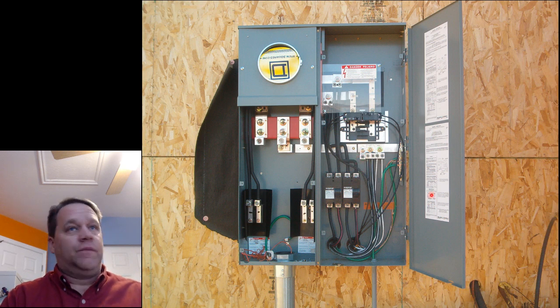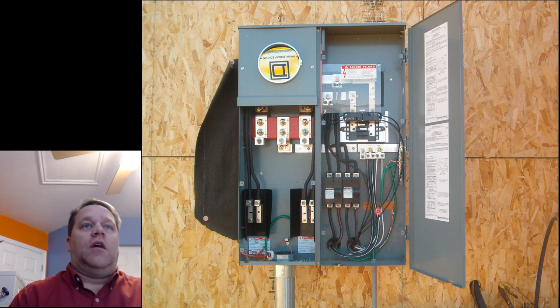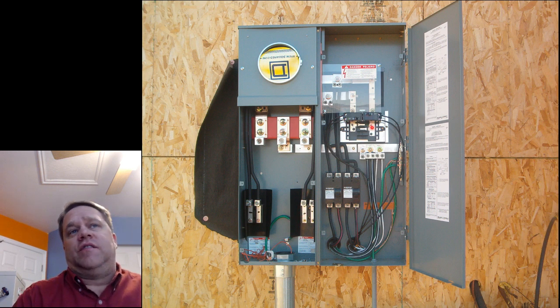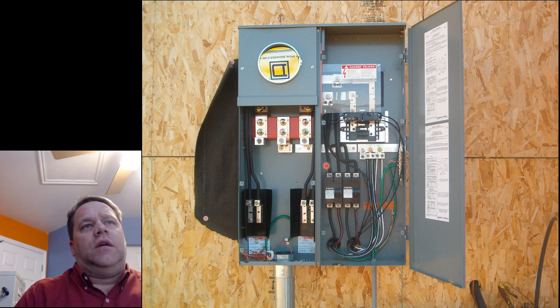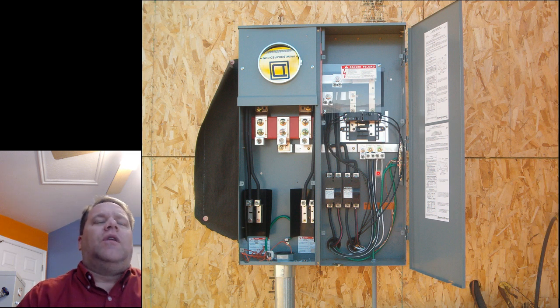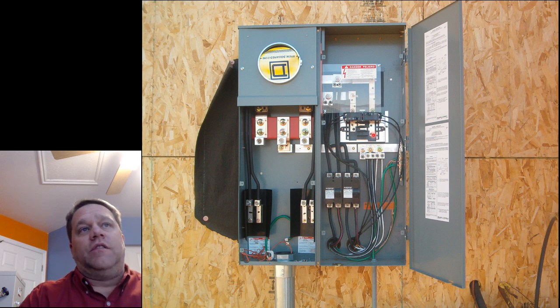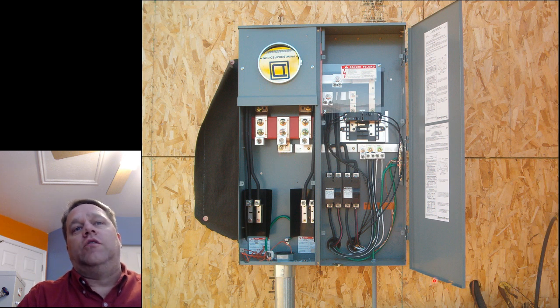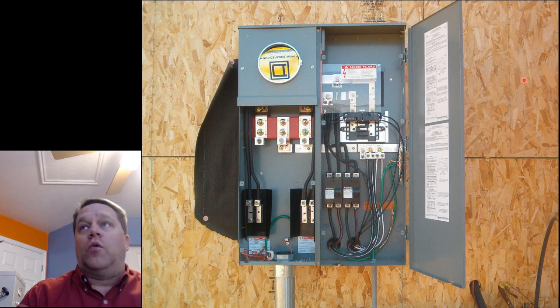Any panel board like this, you can't use it because it's got 1, 2, 3, 4 service disconnects in one enclosure. So the issue again is you'd have to guard all of this equipment. So unless you call the utility, you're going to have energized components inside of this equipment. You can't shut these bus bars off inside this panel unless you call the utility and they remove the meter or disconnect the conductors. And that's what we're trying to avoid. We don't want to have to call the utility to schedule an outage in order to work on a panel.